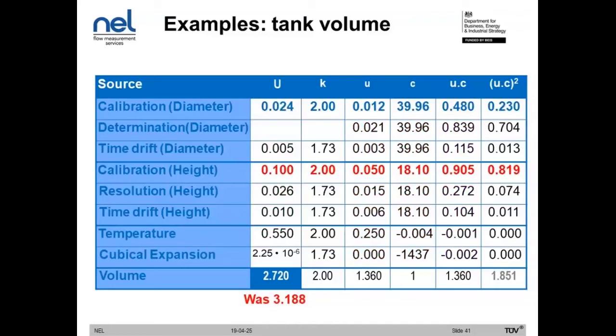We can now see that the largest contribution to the uncertainty is not in the diameter measurement, it's in the height measurement. And again, it's in the calibration of that device. So either replace the device or improve the calibration by calibrating to a more accurate standard. If we spend some more money, we can reduce the uncertainties again.